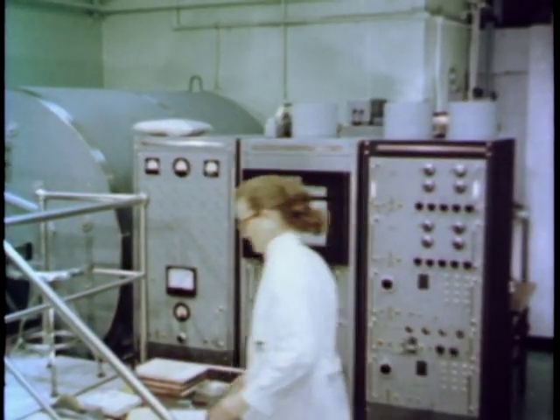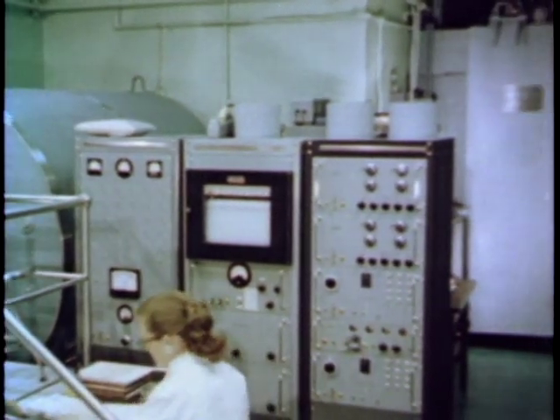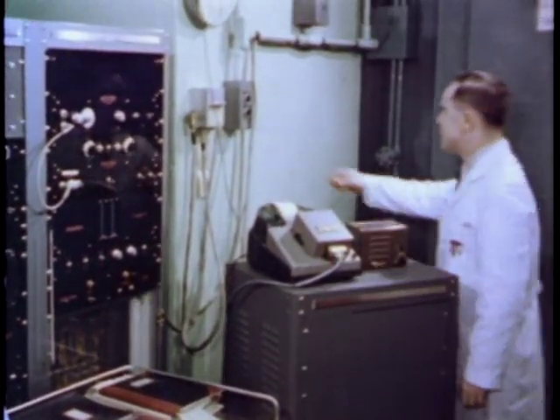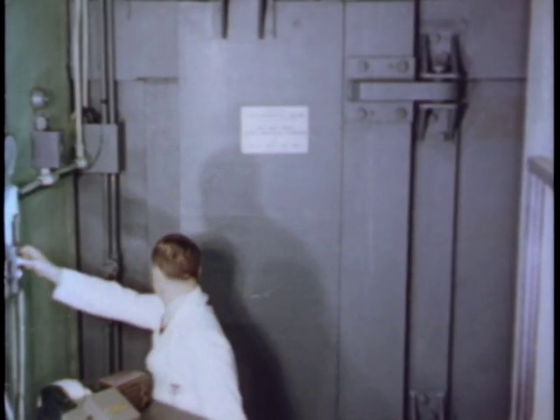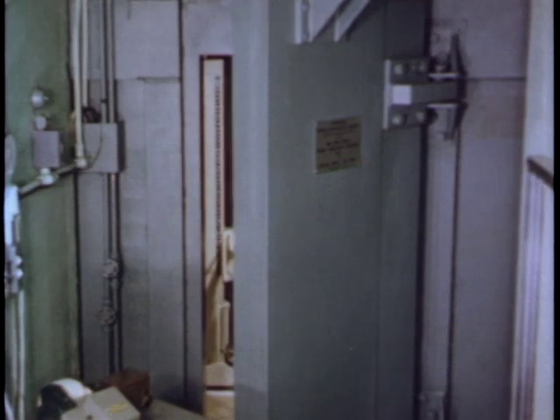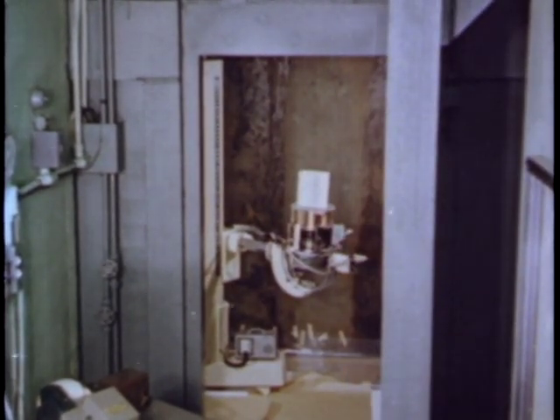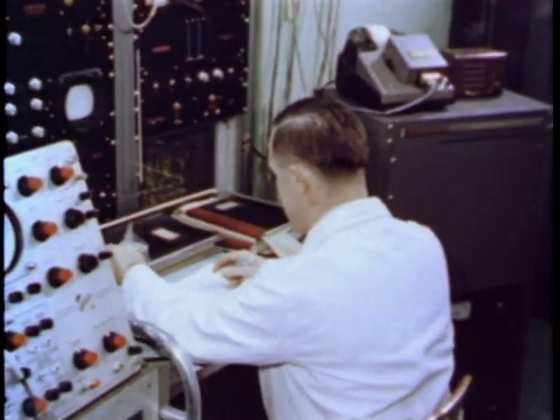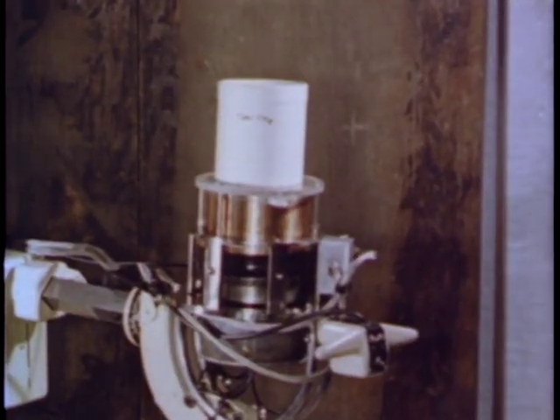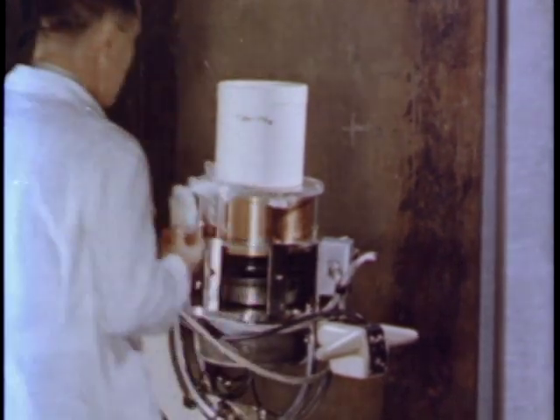To identify absolutely any particular isotope responsible for increased radioactivity in people, the iron room with its associated sodium iodide crystal and multi-channel analyzer was constructed. The iron room, erected from armor plates seven inches thick, measures about 12 by 6 by 7 feet. Overlapping plates cover all joints. Access is provided by a hydraulically operated door weighing approximately eight tons. Constructed to provide shielding to reduce background, the 50-ton room permits measurement of low-level gamma activity.